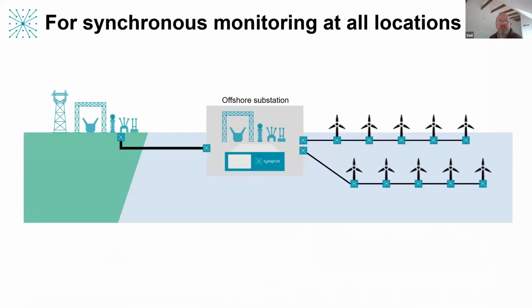what we're saying here is that it is now economically affordable, and from a space and cost and footprint perspective, you can actually instrument every termination and every phase cable termination of every cable and measure discretely all the inputs into the power system that are coming from every single turbine now, to give you live and synchronous control and visibility of what's happening, not just taking an aggregate view of power quality effects and subsynchronous oscillations that might be caused at the grid connection, where arguably that aggregated view hides some of the puts and takes of factors that are out there in the array.